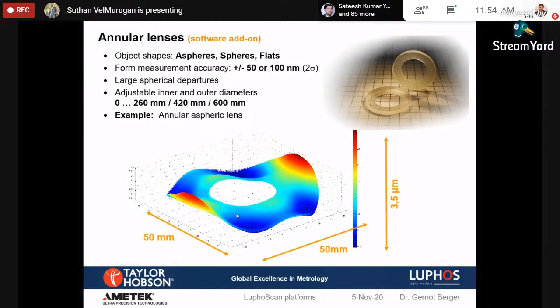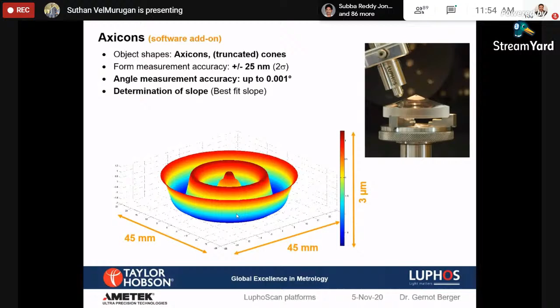And Axicon samples, because it has got a steep slope, will have few limitations on the contact stylus angle. It should not fall on the axicon angle, so it will be lesser. The axicon angle is like 90 degrees, so we need to select a stylus which is less than 90 degrees, probably 60 degrees. But it's a straightforward application in the non-contact. We will not have any limitation.